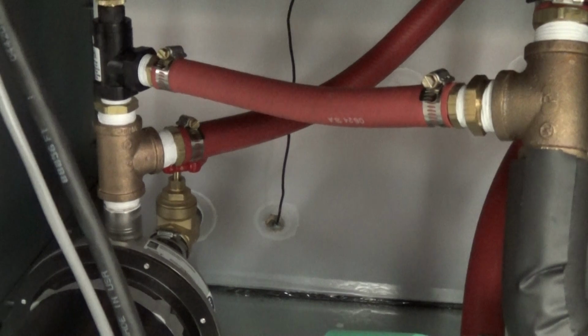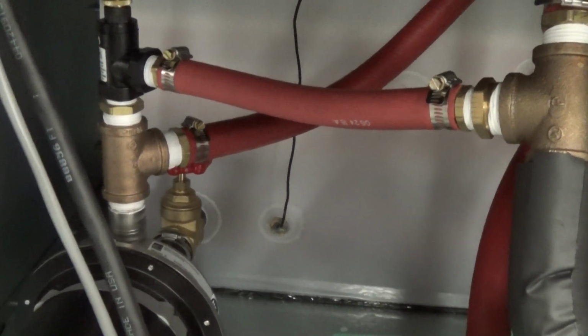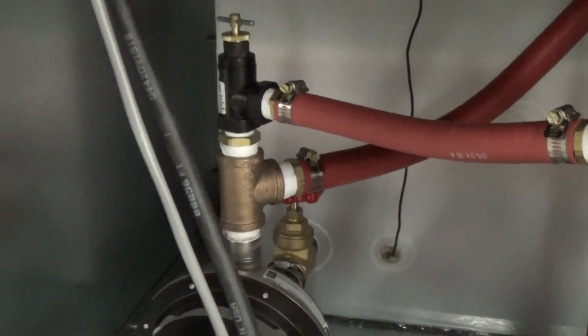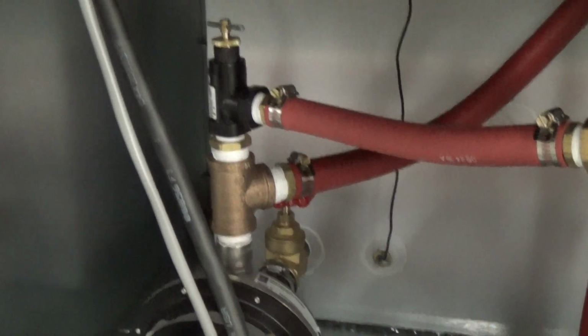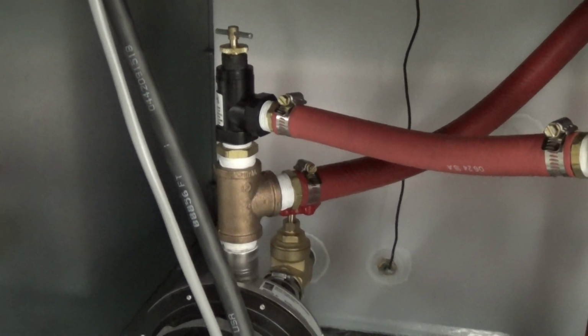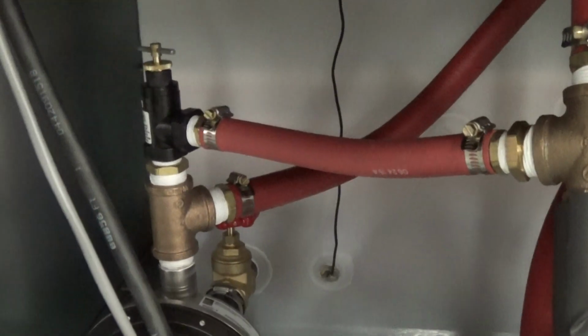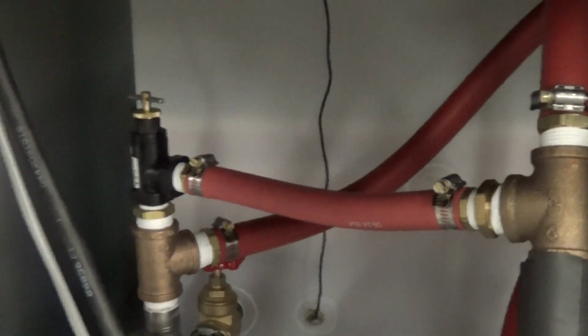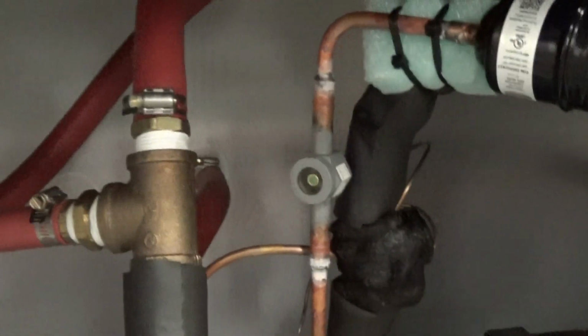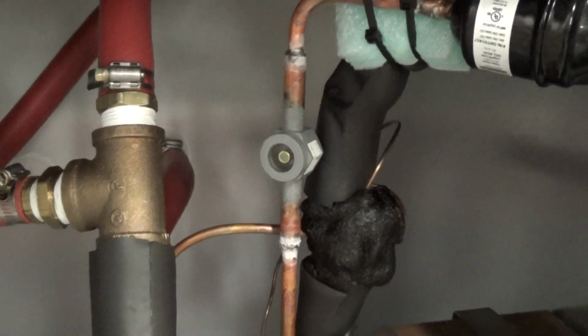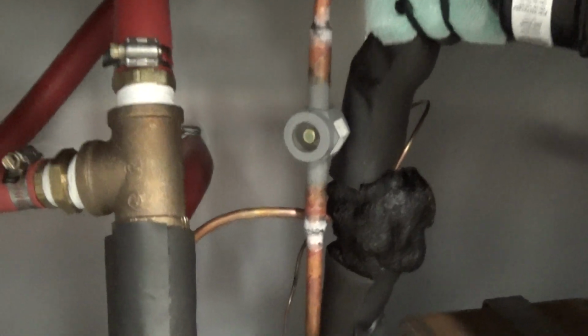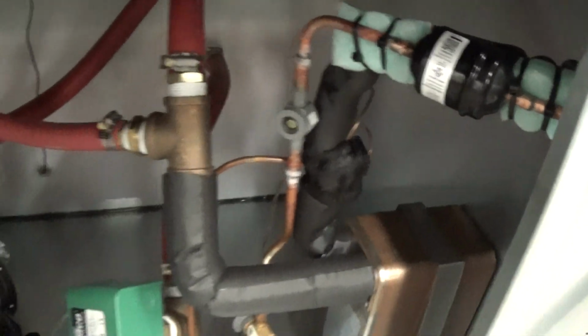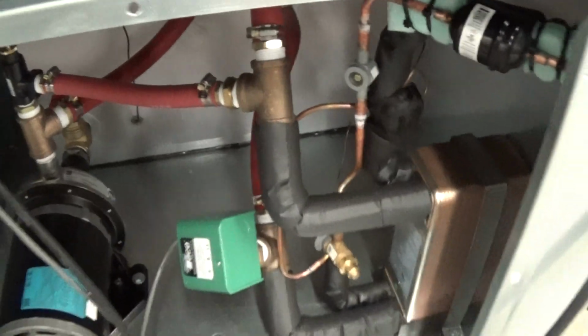If the process has too much restriction, or if you have solenoid valves on your process such that it stops the flow even 100%, then the spring-loaded bypass will open up and we have enough flow that comes back to the heat exchanger to satisfy its flow requirements. You shouldn't have to adjust that bypass. And we have our refrigeration sight glass here, which helps in troubleshooting as far as refrigerant charge goes.